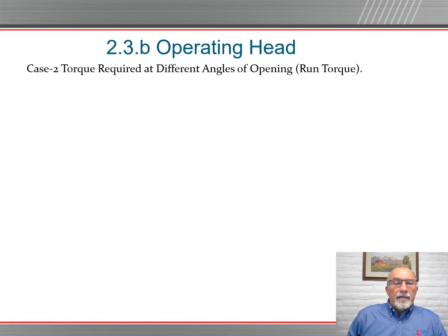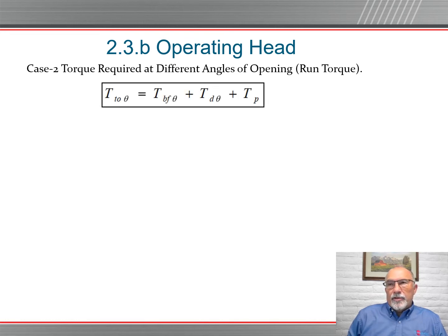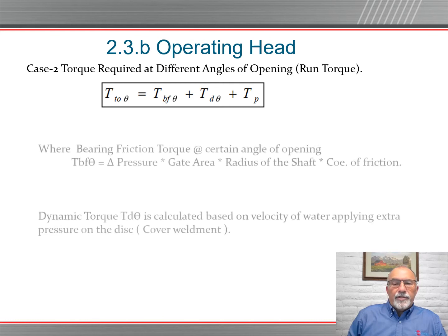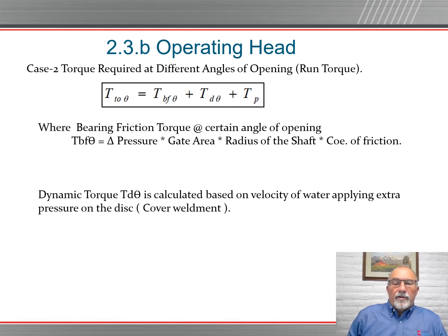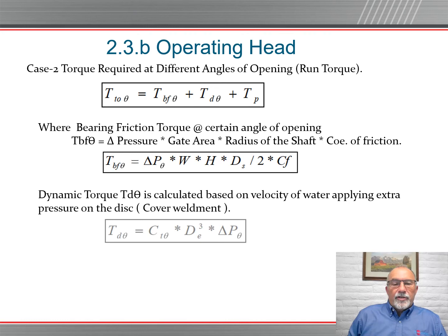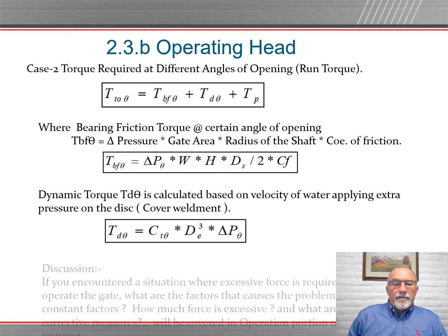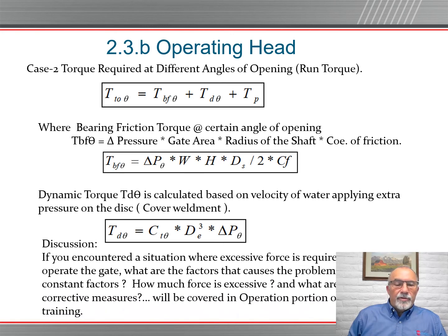The operating head, case number 2, torque required at different angles of opening torque. That's under heavy flow conditions. It can have a big effect on your coefficient of friction by your resistance of your flow. Again, taking into consideration the different causes and effects, we have different calculations that are used.